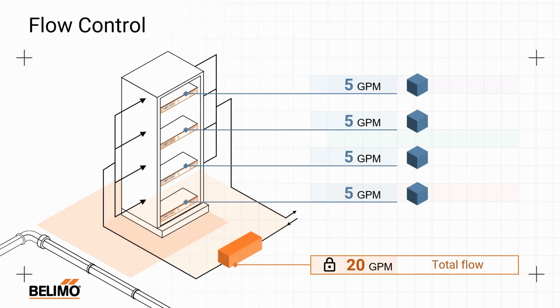Now, if you're sitting at your computer saying that's wildly high flows, I agree. This just makes the math simple. So don't worry about the absolute values of these flows. Just think about this conceptually. So I have a single control valve at the bottom of my loop, and we are controlling the flow to these 4 servers. So I have a total of 20 gallons a minute. The way that this is piped and manifolded up, I'm going to more or less get 5 gallons a minute going through each of those.